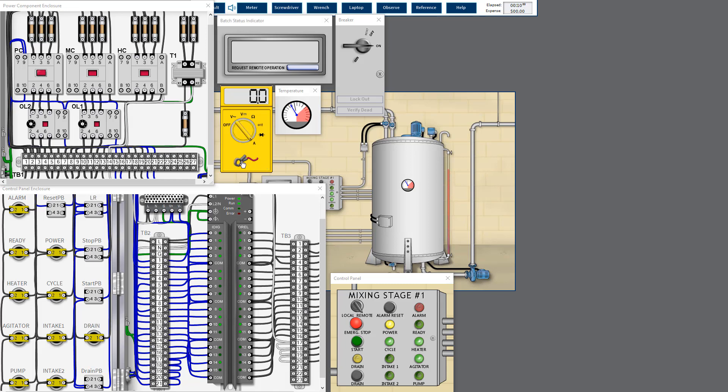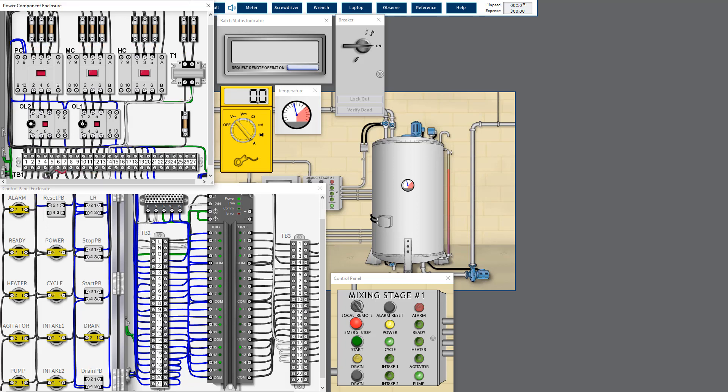Okay, it's best that we can always measure the current, but we know the problem is actually coming from the pump contactor circuit in the control panel, no sorry, in the power panel. So now we don't get any current from two phases and three phases. It's strange because usually we don't get the current in the single phase or the most two phases. Rarely does it occur having the issue of three phases do not have any current. So maybe there's any loose termination or open circuit in three of the lines or two lines.